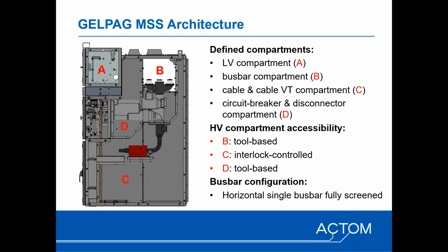So looking at a typical SIS or the GELPAG architecture, as you can see, it's a metal enclosure, as we would be familiar with, with different high voltage compartments. However, there's only one accessible compartment during normal use, and that is the cable connection compartment, which is interlock controlled. The other compartments, which contain the switching device, compartment D, the three-position disconnector and vacuum circuit breaker, effectively incorporated in the SAIEE module, is a tool-based accessible compartment. It's not required to access these compartments during normal use, nor the busbar compartment. It's only needed for installation or dismantling at the end of service. And then, of course, you've got the low voltage compartment.